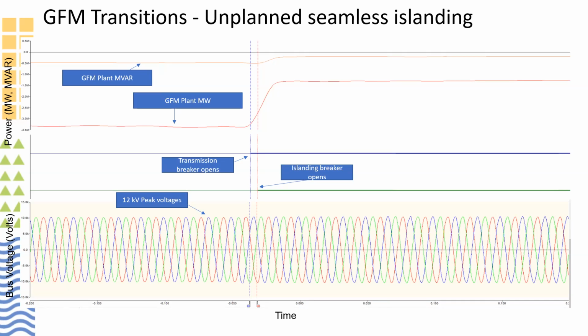In here we have a megawatt and megavar of the grid forming inverter while it was grid connected. We're dispatching, we're supporting grid. We island the system and then automatically it knows where to go. So what we're doing is we take the CTs from the load and we feed that back into the control system. So the control system always knows what that load is, that if it does happen and it needs to island, it knows exactly where it needs to go to for watt and var.